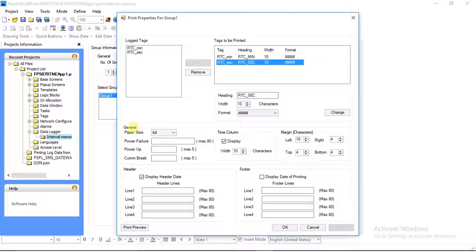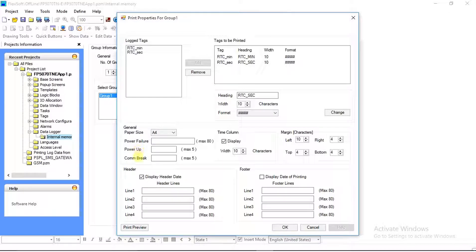In General, paper size is fixed to A4. If the unit is switched off, a power failure message will print. Power-up characters will print the first logged data once the unit gets power. Communication break characters will print only with PLC tags. In Time Column, if the user wants to add a time column, they can do so by selecting the checkbox. In Margin, this is related to the paper margin for 4 sides in printer character size.